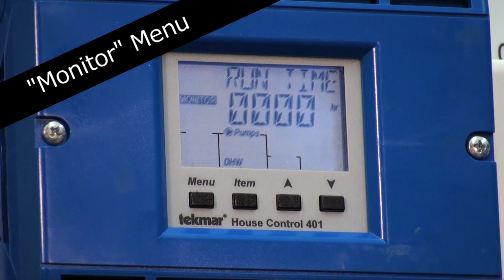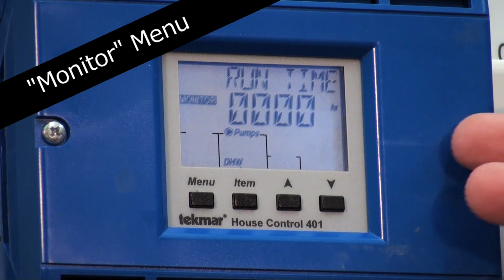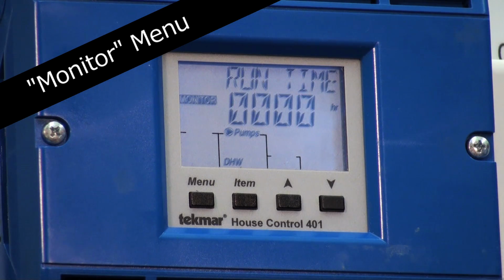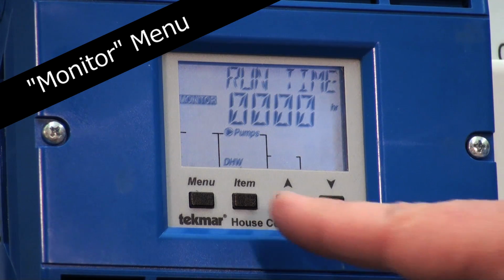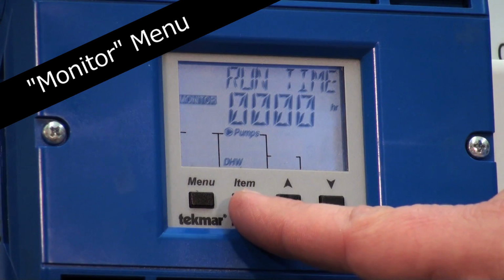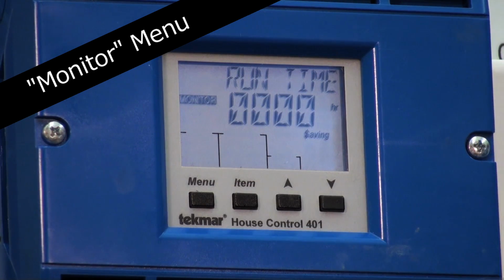Great feature to have when you've got that homeowner that's maybe asking you why it's costing so much to heat their home. You can actually go into the control and get run hours of the boiler and run hours that it's spent in domestic hot water and start to determine if they're taking too many hot tub baths.